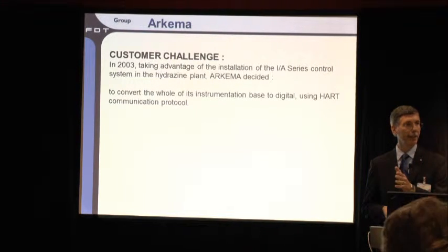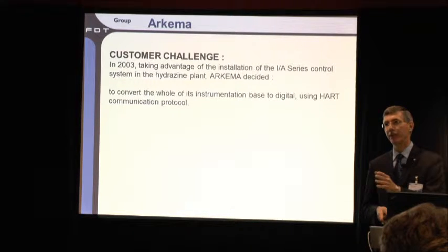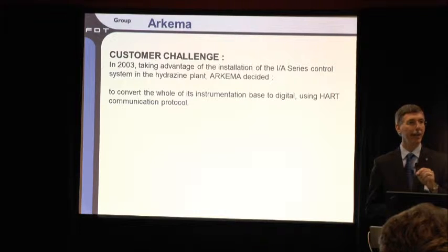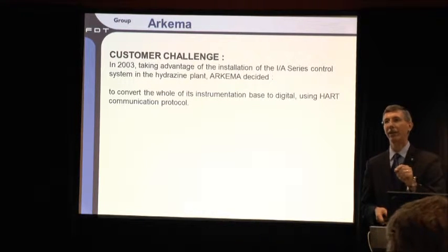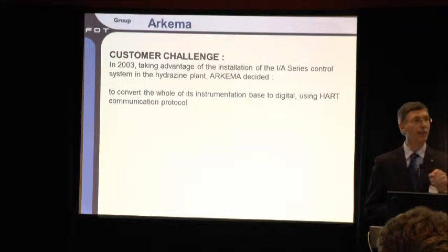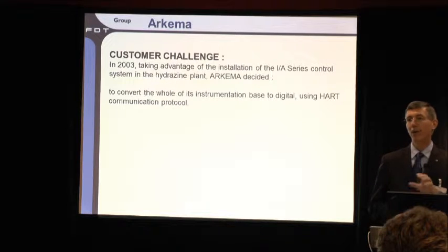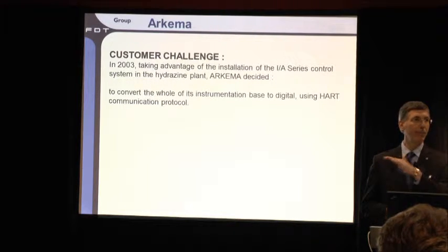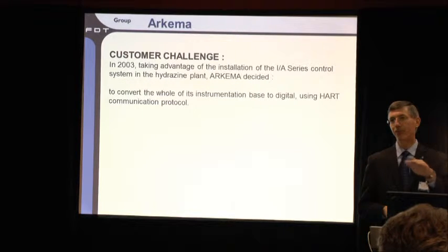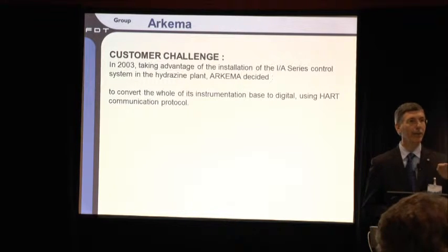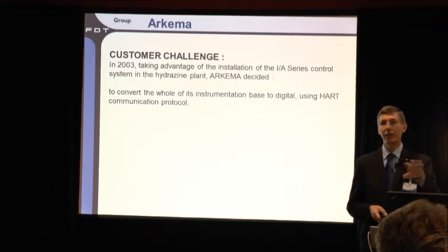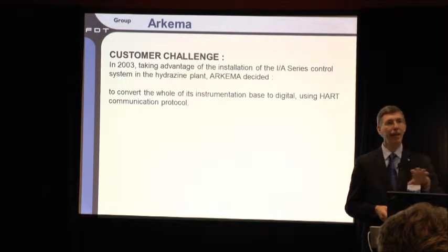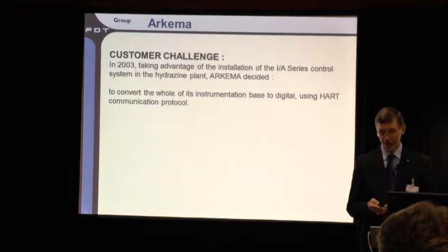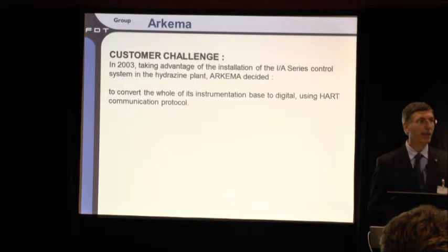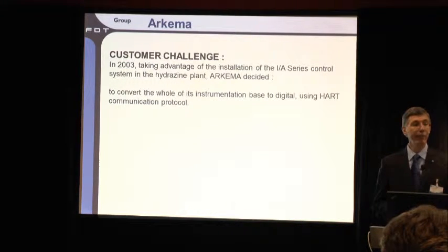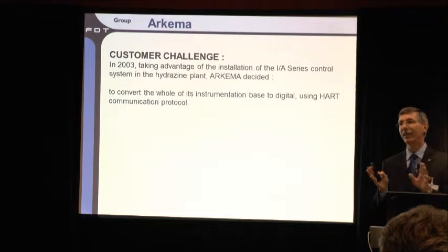So they went with HART in their case. For those not familiar with HART, briefly - it's really the old 4 to 20 milliamp instruments, a current loop instrument, and the primary process value still comes via that current loop, a measured current loop in a 4 to 20 milliamp range. But what makes it effective as HART is that they put a digital signal on top of that 4 to 20 milliamp signal, so on the same pair of wires you can superimpose this digital signal. Now you can communicate with that device digitally and start to get diagnostics, advanced configuration, and other things. That's the HART network - probably one of the most widely installed communications protocols. Most people familiar with it would be quick to say, let's be clear though, HART technically isn't a network.